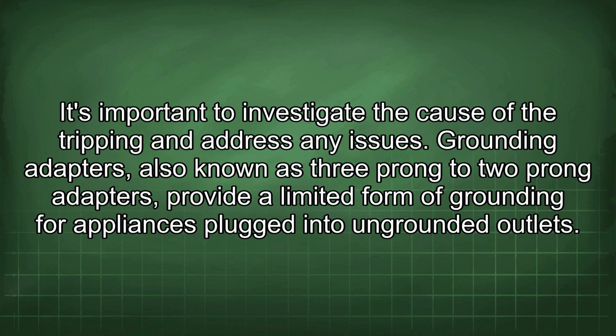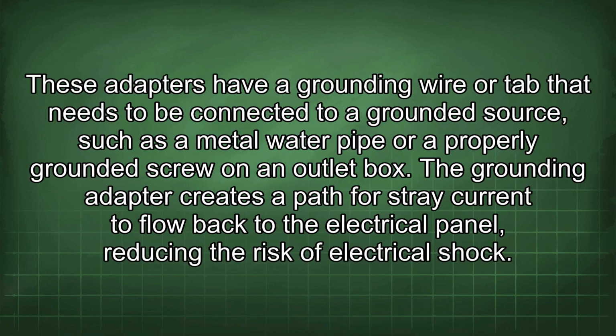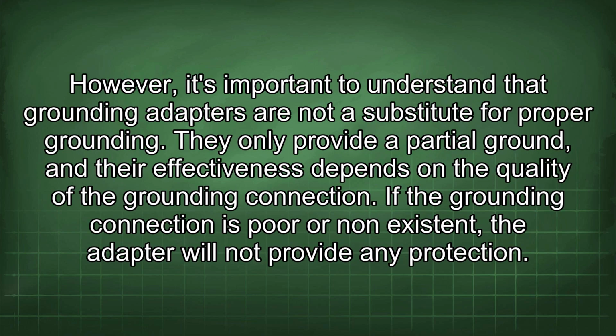Grounding adapters, also known as 3-prong to 2-prong adapters, provide a limited form of grounding for appliances plugged into ungrounded outlets. These adapters have a grounding wire or tab that needs to be connected to a grounded source, such as a metal water pipe or a properly grounded screw on an outlet box. The grounding adapter creates a path for stray current to flow back to the electrical panel, reducing the risk of electrical shock. However, it's important to understand that grounding adapters are not a substitute for proper grounding. They only provide a partial ground, and their effectiveness depends on the quality of the grounding connection. If the grounding connection is poor or non-existent, the adapter will not provide any protection.